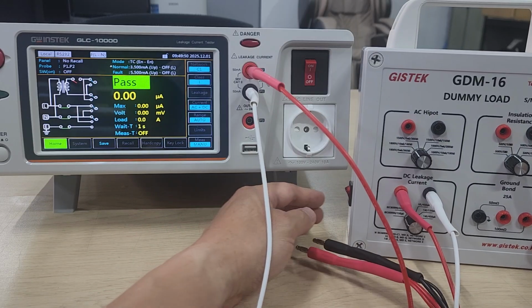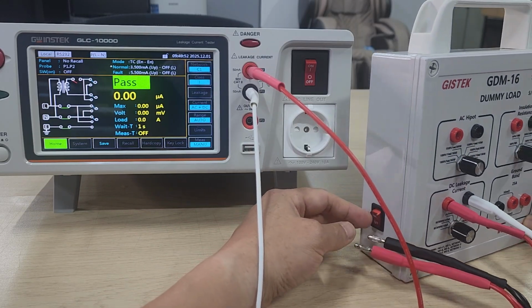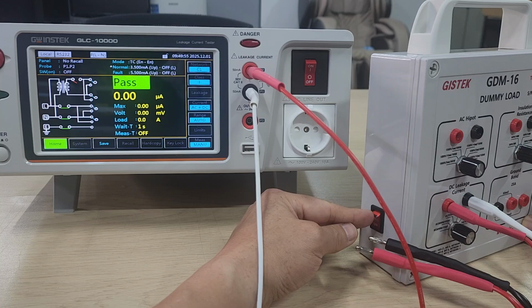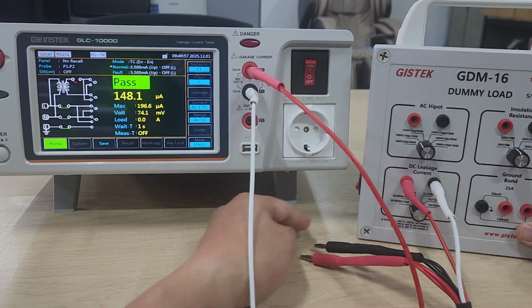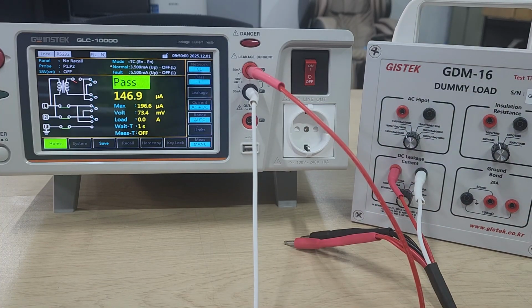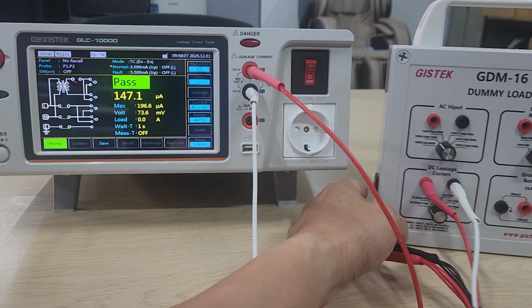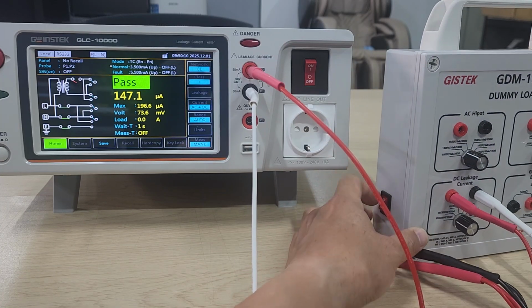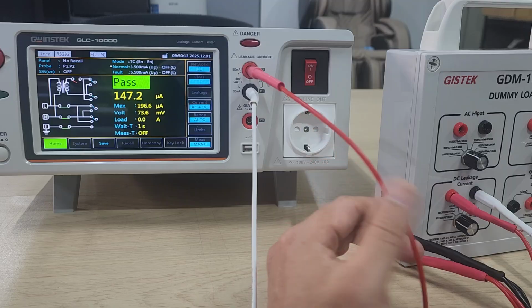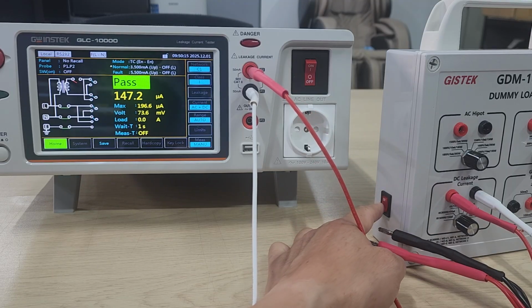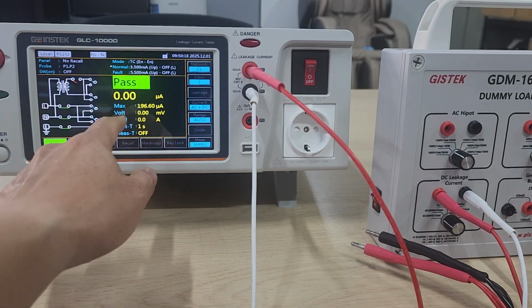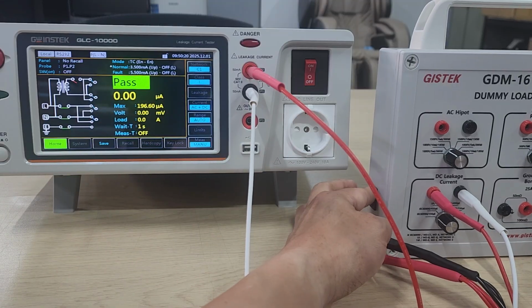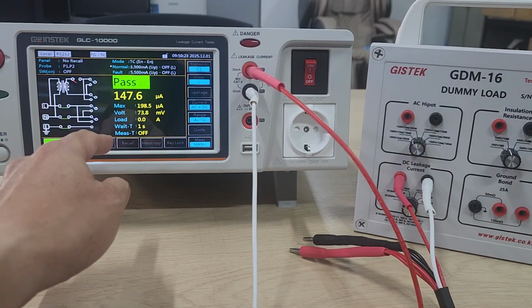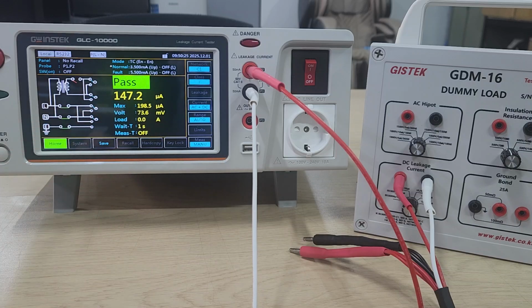Now it is zero testing. Turn the power on for the DC current tester function. Turn the dummy load leakage current output button, here, on. Turn off: test is 0. Turn on: approximately 150 microampere.